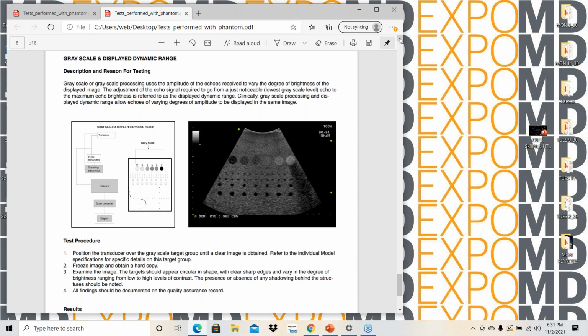This one, oftentimes, it's really difficult to see. You may not see it. It may barely be there. And why is that? Because the system, not the probe, can't resolve the difference between the average and the density of that, which is only 3 decibels difference. This is positive 3 decibels, this is negative 3 decibels, and this is 0 decibels. So when the system itself can't resolve down to differentiate them, they won't be displayed. So that's really what you're looking at, okay?